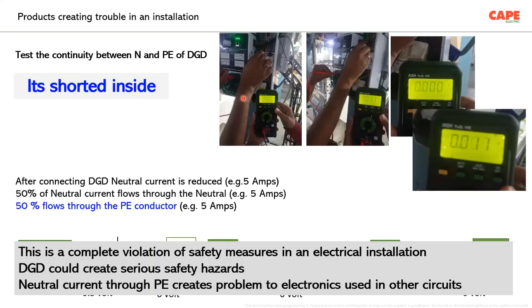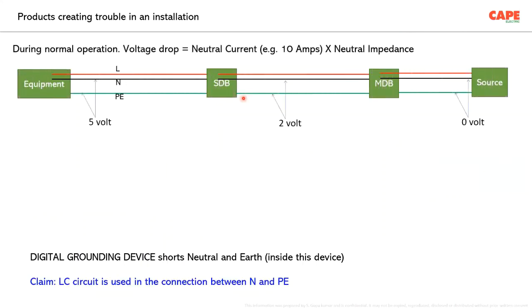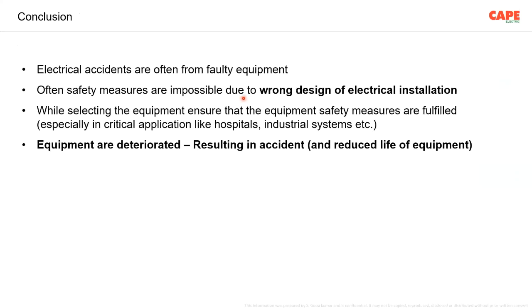Please understand that the electrical safety regulation, the CEA regulation measures relating to safety, demands 1 mega ohm insulation resistance between neutral and earth within your building. If you install this kind of a device, that's gone. So the operation of this device, I don't want to explain. So with this, I make the conclusion.